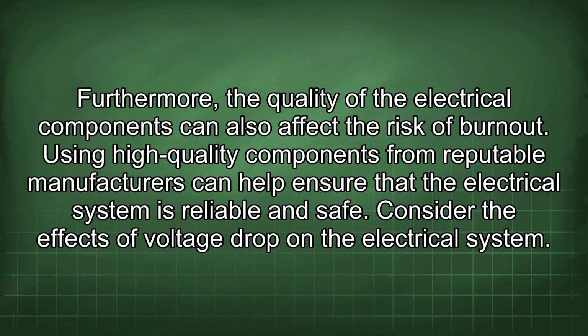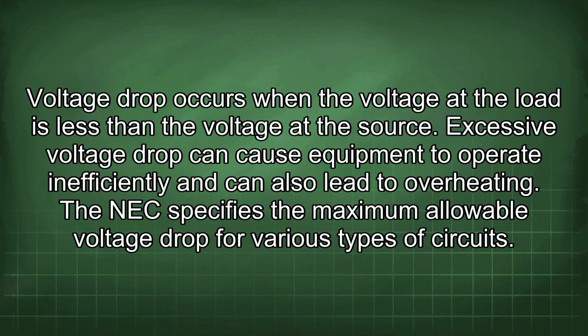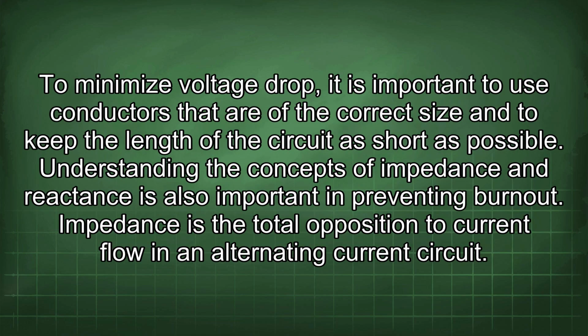Consider the effects of voltage drop on the electrical system. Voltage drop occurs when the voltage at the load is less than the voltage at the source. Excessive voltage drop can cause equipment to operate inefficiently and can also lead to overheating. The NEC specifies the maximum allowable voltage drop for various types of circuits. To minimize voltage drop, it is important to use conductors that are of the correct size and to keep the length of the circuit as short as possible.